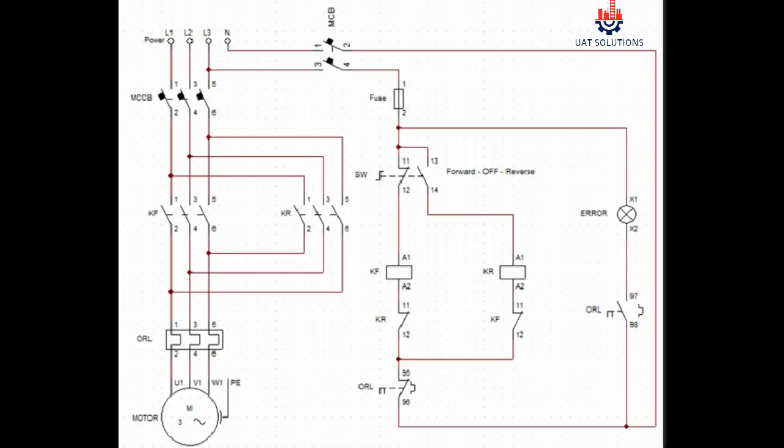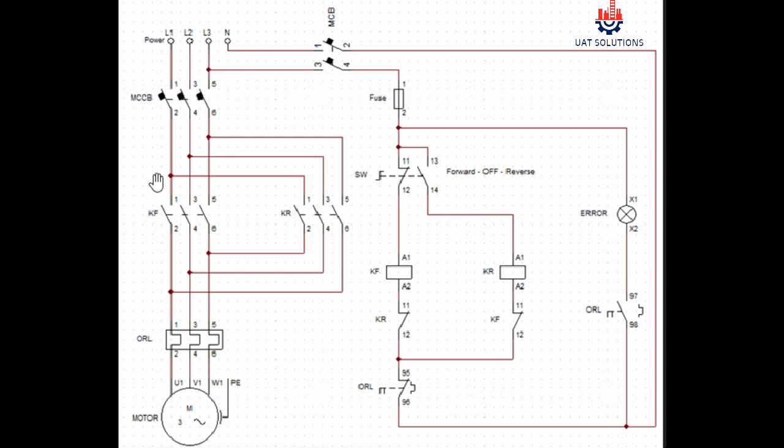Three phase respectively L1, L2, L3 are supplied through the main circuit breaker to the input terminals 1, 3, and 5 of contactor KF used for forward function and contactor KR used for reverse function.